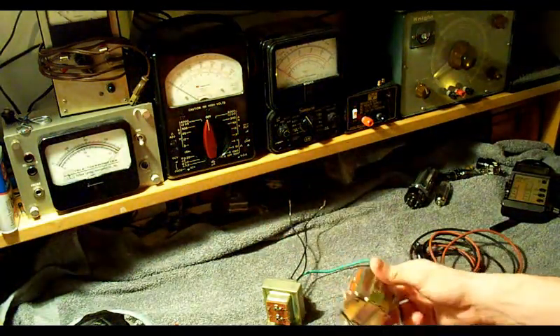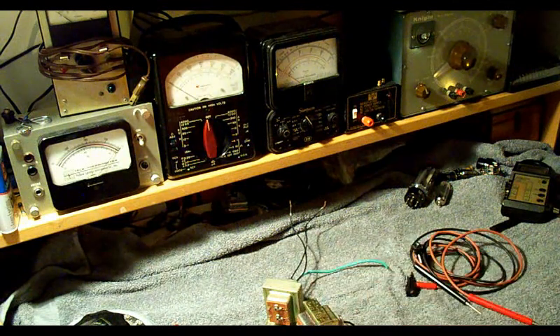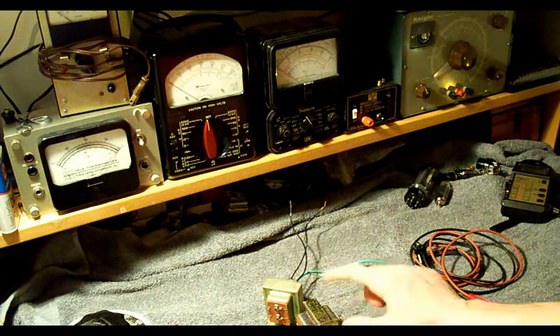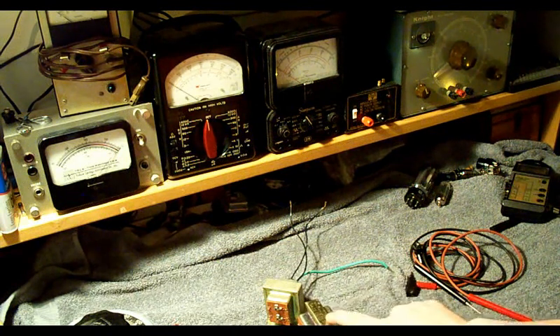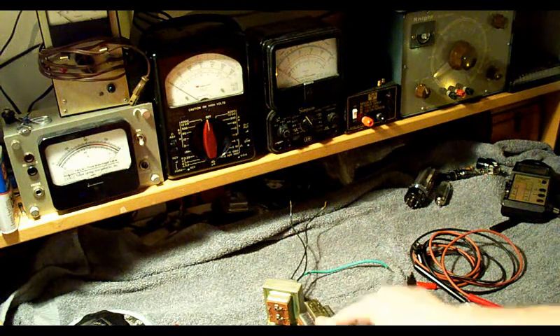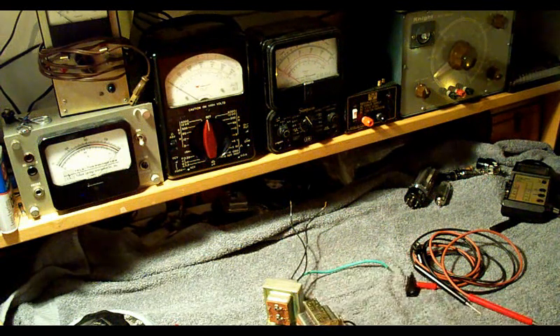So that was just a quick video I wanted to make on why it's always important that anytime you get any type of transformer, before you apply power to it, always check with an ohm meter or a continuity buzzer. Check the continuity of the windings, check the continuity of the windings to the other windings, and also, importantly, check the continuity of each winding to the case or the ground, because if the case isn't grounded and one of the wires were to touch this metal frame, whatever this transformer is mounted to would then become energized. But if it's grounded, then of course you would trip a breaker.